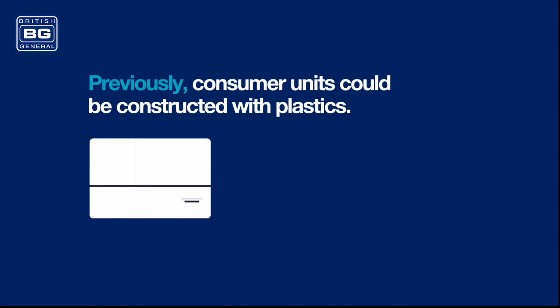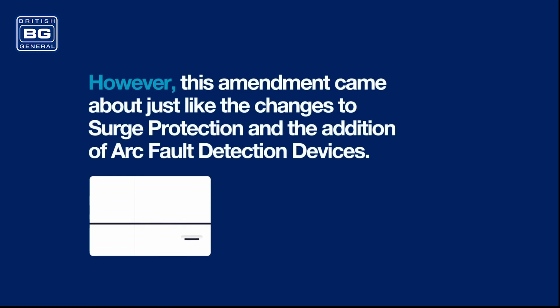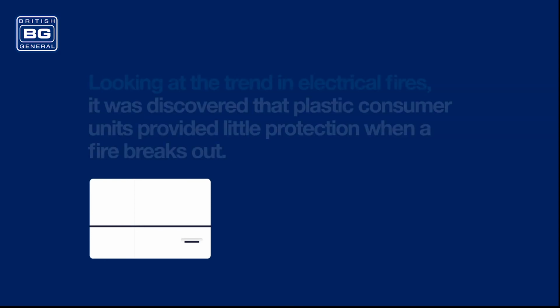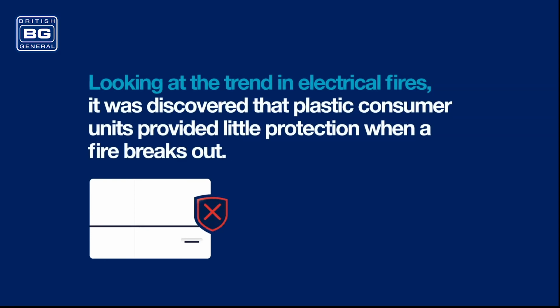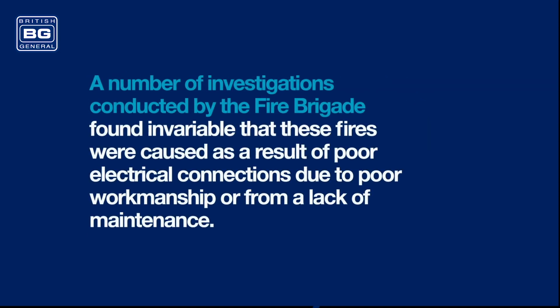Previously, consumer units could be constructed with plastics. However, this amendment came about just like the changes to surge protection and the addition of arc fault detection devices. Looking at the trend in electrical fires, it was discovered that plastic consumer units provided little protection when a fire breaks out. A number of investigations conducted by the fire brigade found invariably that these fires were caused as a result of poor electrical connections due to poor workmanship or from a lack of maintenance.